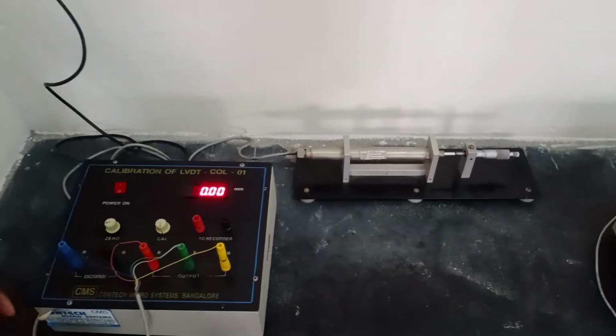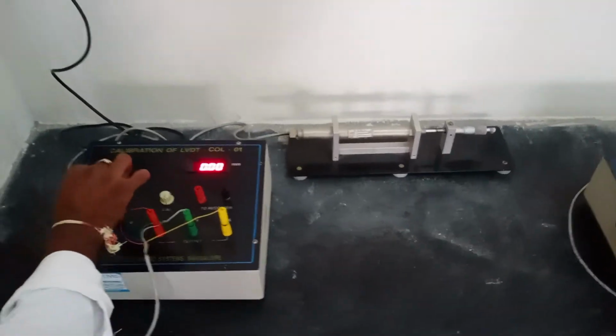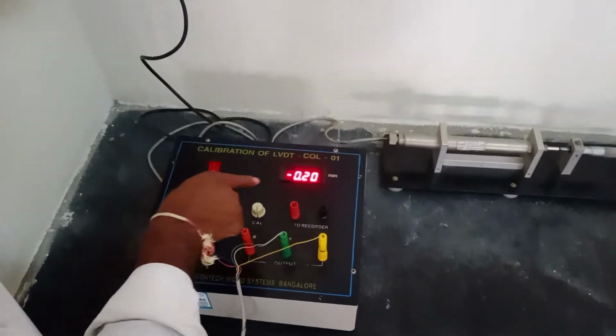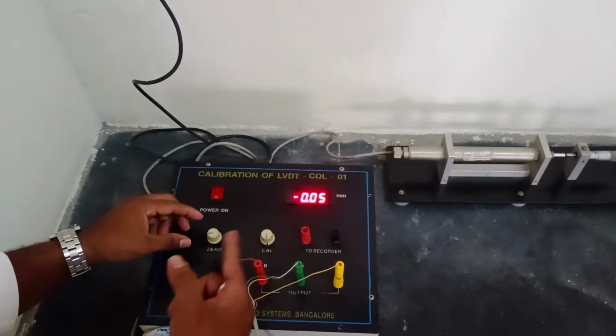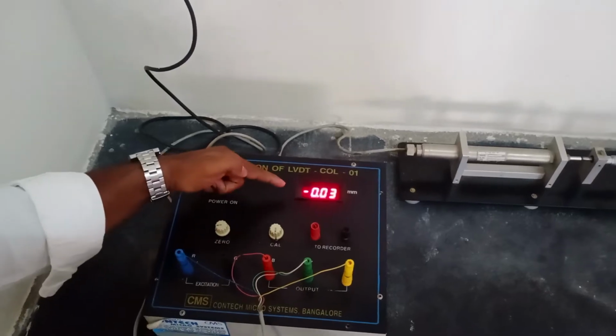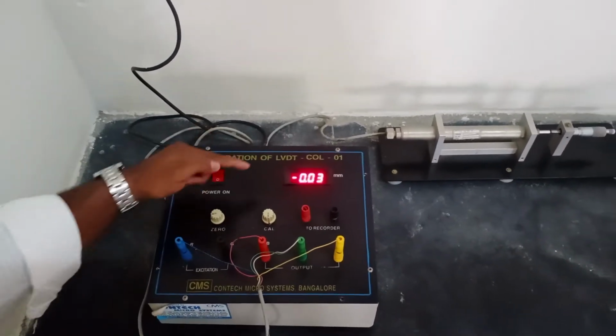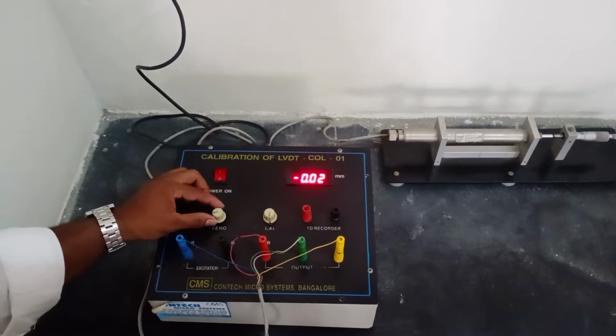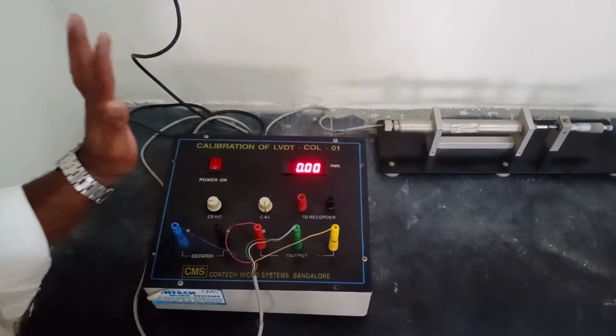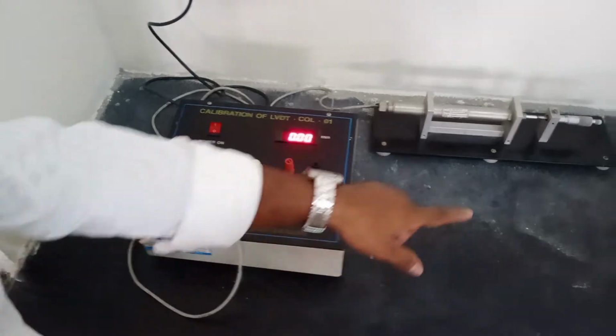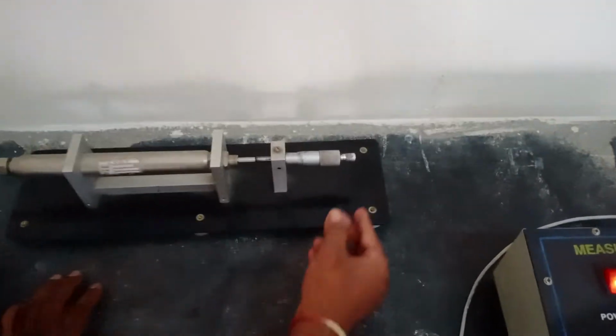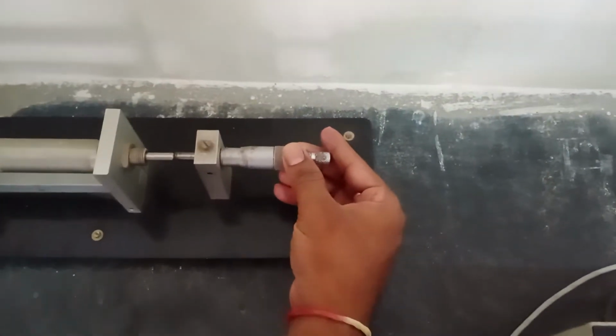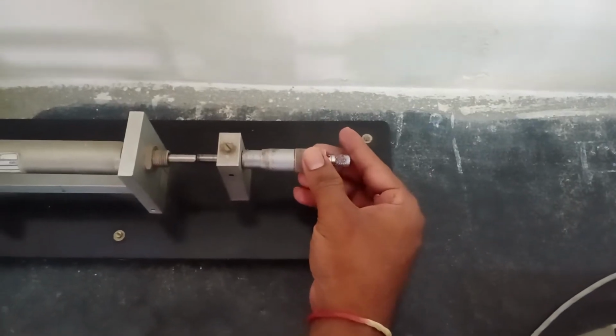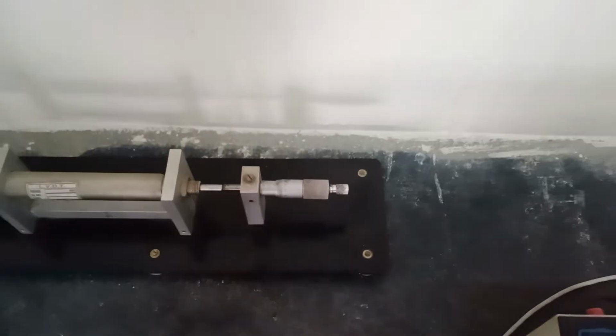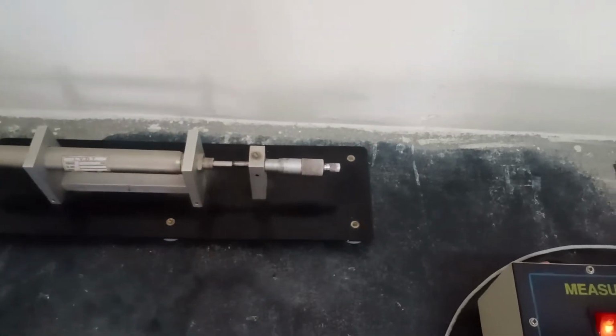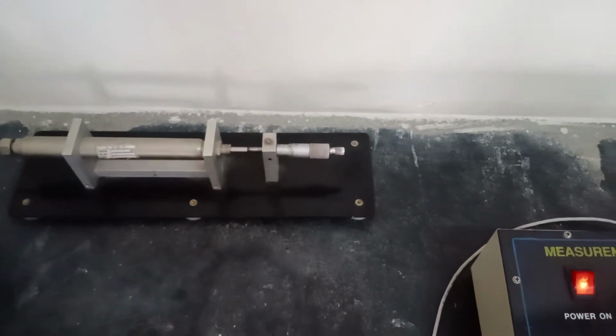First we are going to make the display zero before calibrating, by operating the knob. We have to make the digital display show 0. Next we go for the micrometer. The distance should be 10 mm. Why? Because 10 mm is the null point, which means the exact center point. There the voltage is going to be 0.